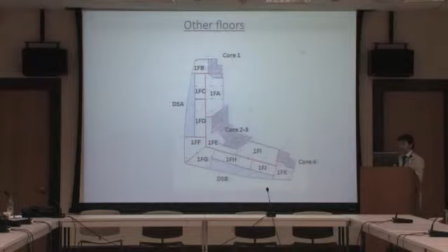As for the internal gains, we used this shape on the left, this internal gain shape, which is quite usual. There are many works in literature showing that buildings are never 100% occupied, and based on some literature studies, we could put this kind of people distribution. That means the average value of occupancy hours is about 63% from 8 a.m. till 7 p.m. This is how we consider the load distribution for the other gains, which are lighting, PCs, and some other electric gains.